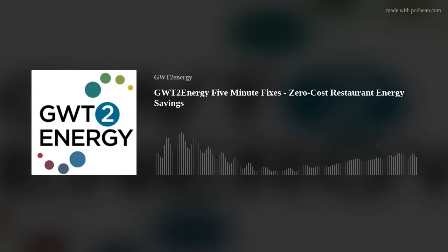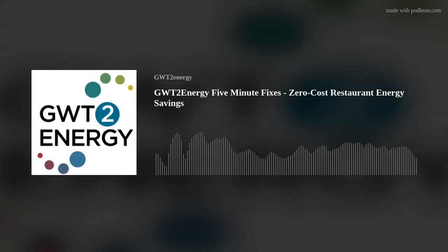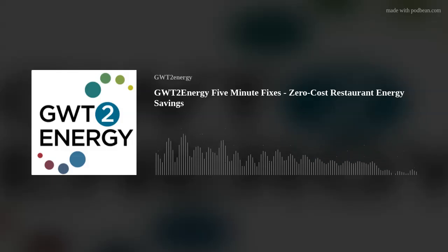So once they identified the problem with the meter data, the goal was simple. Bring that overnight energy floor down by reprogramming, not replacing. Exactly. And they organized it around 3 zero-cost fixes. Let's start with the heavy hitter, especially in the South: HVAC scheduling. As I said, HVAC is the single largest consumer of energy in a hot climate QSR. The error they found was incredibly common. Somewhere along the line, probably due to a temporary maintenance need or a staff change, the system had been programmed to a permanent occupied mode.